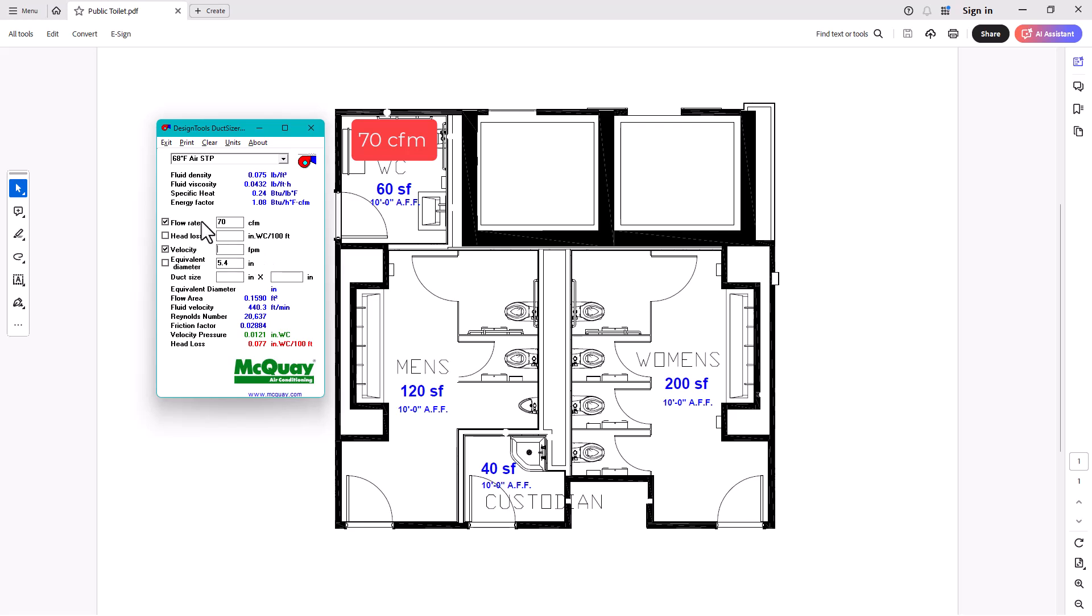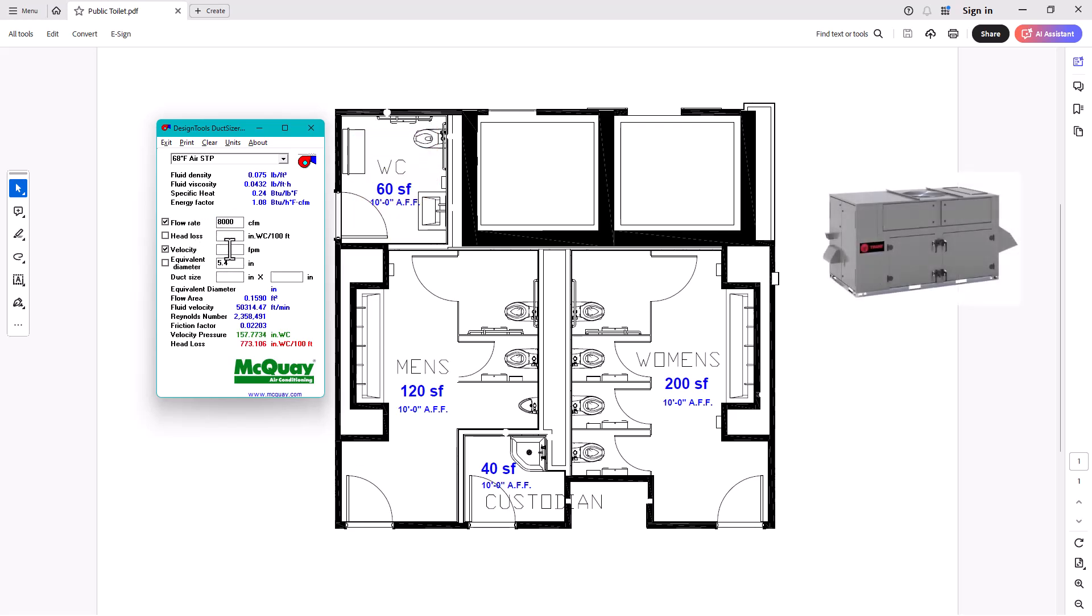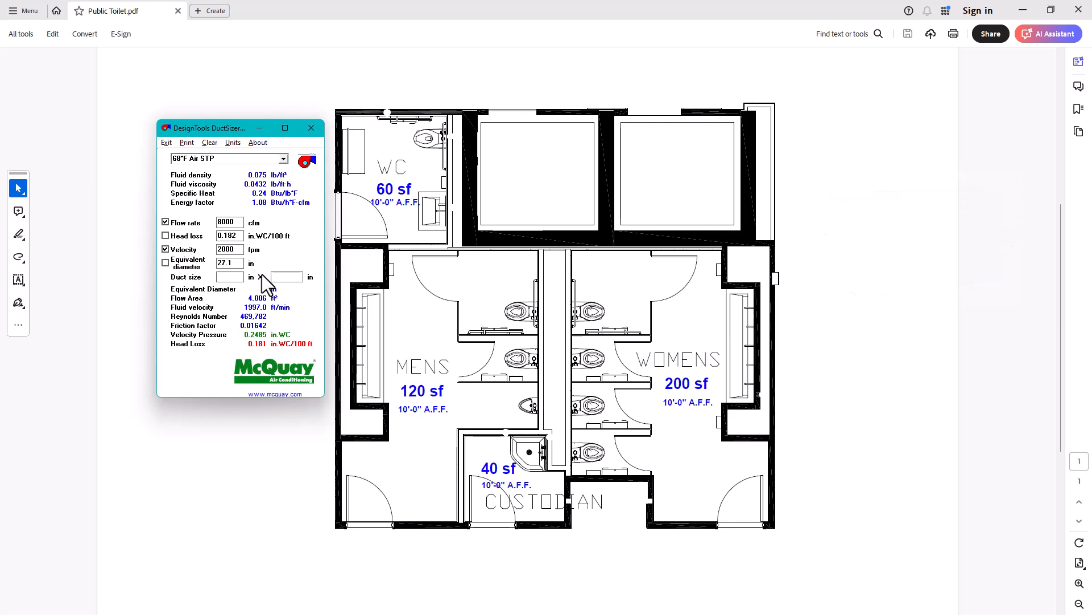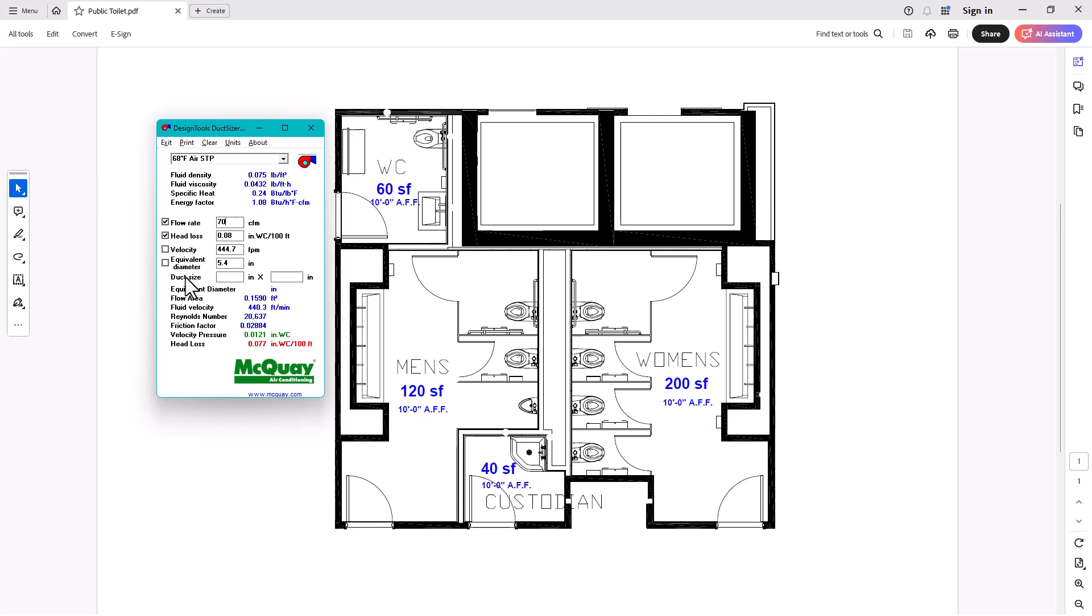In some cases, you're gonna need the velocity. So you can either size this by friction rate, head loss, or you can size it by velocity, velocity FPM. So usually that happens when you have, for example, a DOAS system. Oh my gosh. So this is going to be, for example, 8,000 CFM, a big unit in the rooftop. So if you have 8,000 CFM, instead of doing friction, we're going to be sizing the ducts based on FPM in velocity, because those are going to be medium pressure ducts. So in medium pressure ducts, we're going to have 2,000 FPM, and then you can size your ducts based on that. But now, maybe in another video, we're going to be talking about low pressure ducts and medium pressure.